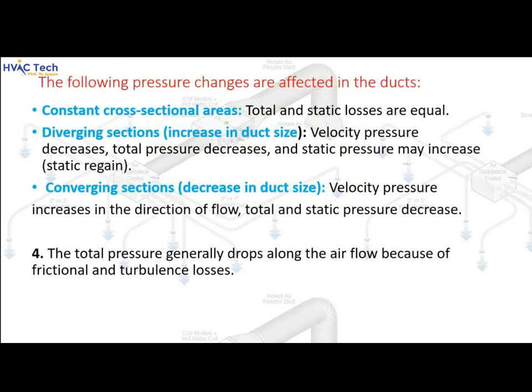The following pressure changes occur in ducts: in constant cross-sectional areas, total and static losses are equal. In diverging sections — an increase in duct size — velocity pressure decreases, total pressure decreases, and static pressure may increase (static regain). In converging sections — a decrease in duct size — velocity pressure increases, while both total and static pressure decrease. Total pressure generally drops along the airflow due to frictional and turbulence losses.